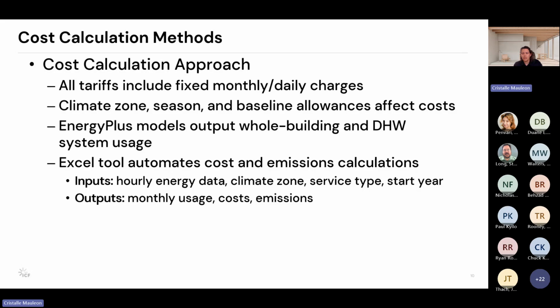This is showing how we calculated the energy costs and emissions for each domestic hot water system. So we accounted for all fixed charges in the rate tariffs and considered how the climate zone, the season, and the baseline allowances influence costs in each hour. The EnergyPlus models provided detailed energy use for the entire building and also for the domestic hot water system by itself. To streamline the analysis, we used a custom Excel tool by entering hourly energy data, climate zone, service type, and start year. That tool generates monthly breakdowns of energy consumption, fuel cost, and emissions.